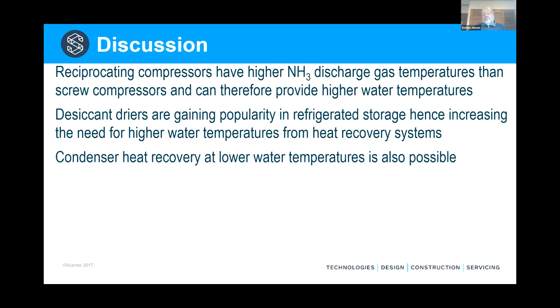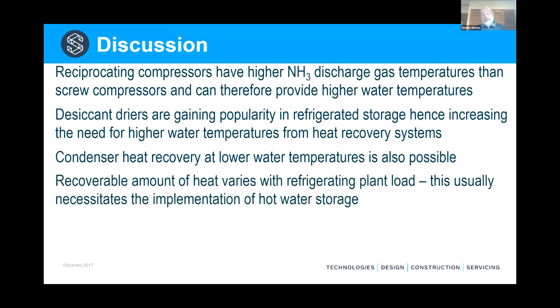We can also recover the 88% condenser heat, of course, but that is at a much lower temperature, and it may be a problem finding a use for those lower temperatures unless another high temperature heat pump is added to the system, like Jared was alluding to before. The recoverable amount of heat, of course, varies with the plant load. We try to make part load performance highly efficient, because that saves energy on the refrigeration plant. And when the plant reduces in load because it's nighttime or it's a holiday or whatever the case might be, then we need to accommodate that. And this usually happens with storage. So we have hot water storage so we can overcome those periods of low load where we don't recover as much heat as we can at full load.